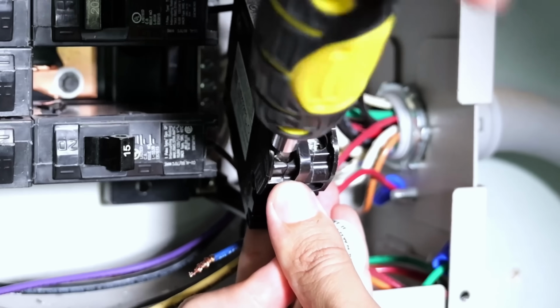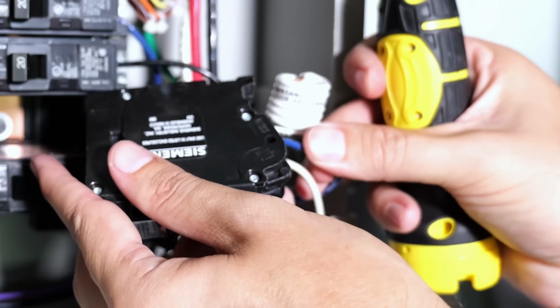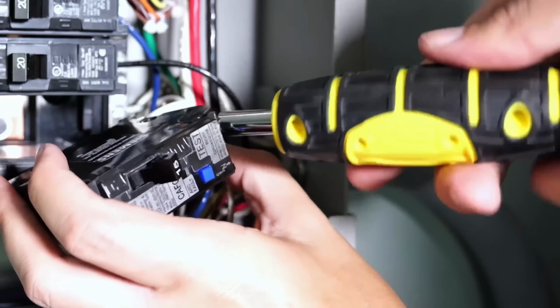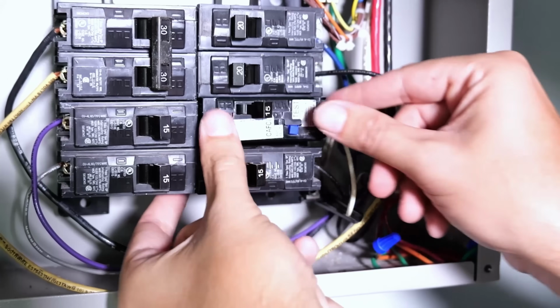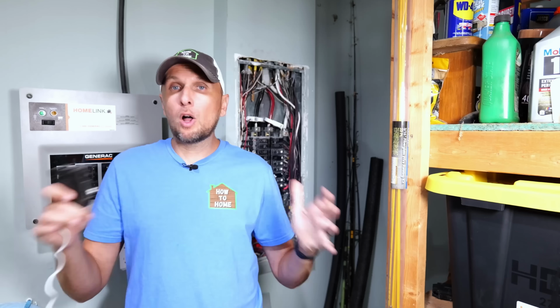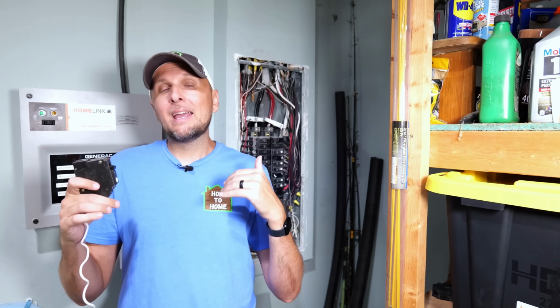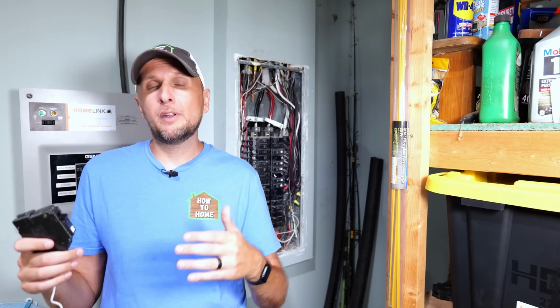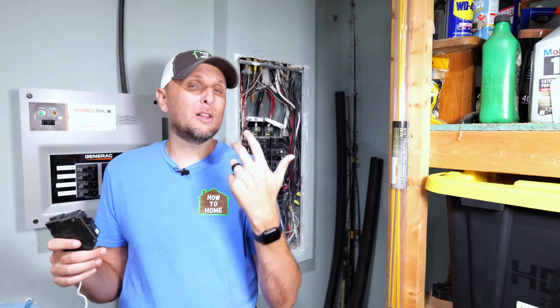One unfortunate thing is your regular circuit breakers are very inexpensive, whereas AFCI circuit breakers aren't cheap. But the good news is they're fairly easy to install. Once all those steps have been followed, the circuit now meets code and is protected from any arc faults, and therefore from the possibility of fire, shock, or even electrocution.